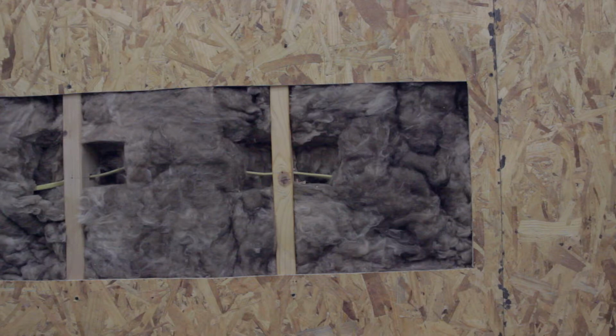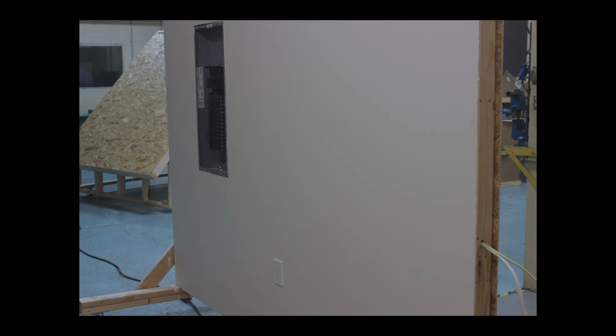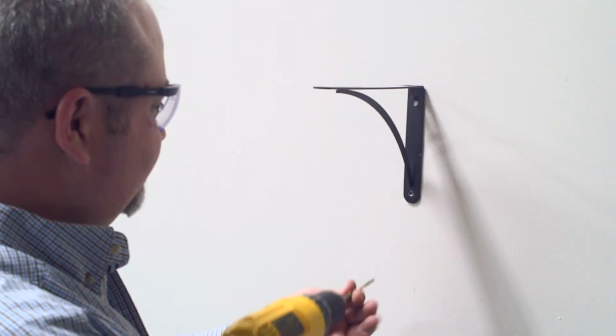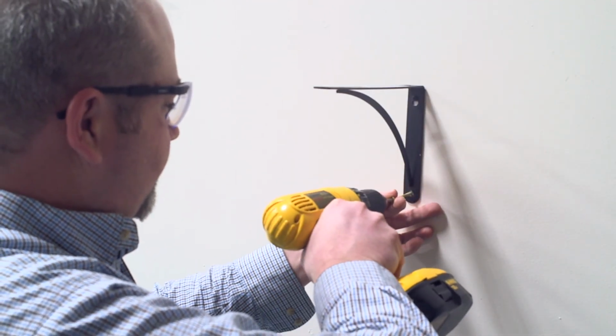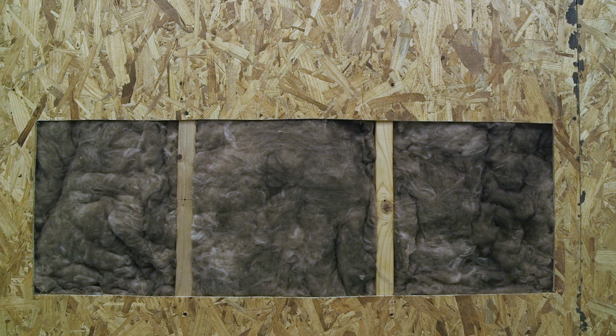The first model simulated a real exterior wall constructed using standard insulation, 2x4s, wallboard, NM cable installed per the code, and exterior sheathing. We used the maximum length of NM cable from the panel to the first outlet box permitted by the NEC, and 500 amps of available short-circuit current at the panel, per the UL AFCI standard. 3-inch screws were used to penetrate the wall and were centered on a stud. We cut away part of the wall for video recording of the results.